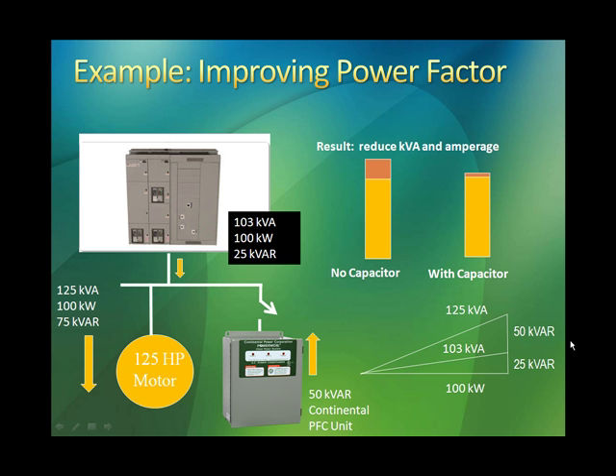There's a couple of things that I want to point out here. One is we never have to add as much kVAR as is being used in the system. Our goal is to get the power factor up to around 95 to 97%. It's been written about many times by electrical engineers, authors that write in the IEEE journal, that bringing the power factor up to unity, or 100%, is a waste of money, because with just providing 2/3 of the capacitance in this example, we can bring the power factor up high enough where we have very, very little reactive energy. And this is also a benefit if some of the motors in the facility are turned off. You won't put the facility into a leading condition that way.